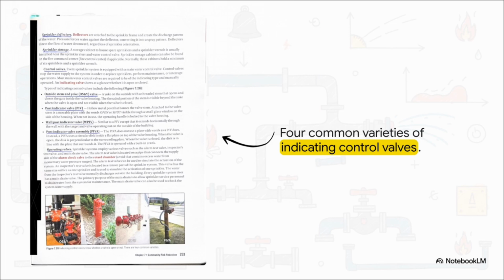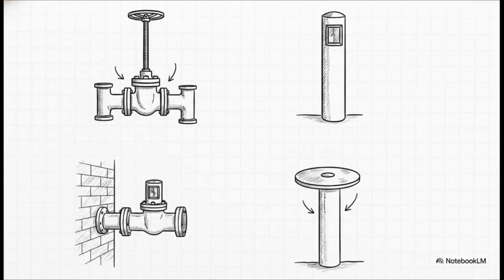So the absolutely crucial point here is control. When firefighters arrive on the scene, they need to know instantly, without a shadow of a doubt, if the building's water supply is open and active or if someone accidentally left it closed. That is exactly why every system is equipped with main water control valves of the indicating type. An indicating valve visibly shows you at a mere glance whether it is open or closed. There are 4 common varieties that fire professionals literally have to memorize. Let's rapidly decode these visual tells so you can spot them like a trained inspector.